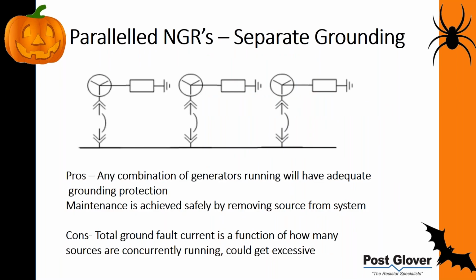Paralleled NGRs, separate grounding—there are different ways to configure this. This is with generators, but it could be with transformers. The only difference, honestly, is there's going to be some harmonic issues potentially with generators that you wouldn't have from transformers, but otherwise they act very similarly. Obviously I have generators pictured here, but for most intents and purposes you could switch those out with transformers.